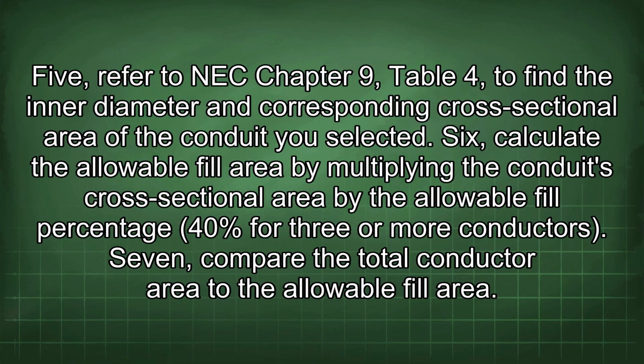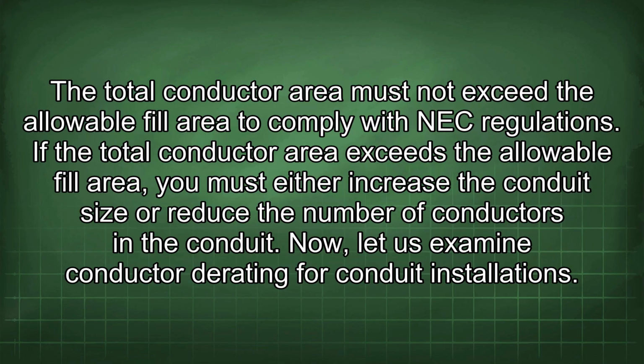7. Compare the total conductor area to the allowable fill area. The total conductor area must not exceed the allowable fill area to comply with NEC regulations. If the total conductor area exceeds the allowable fill area, you must either increase the conduit size or reduce the number of conductors in the conduit.